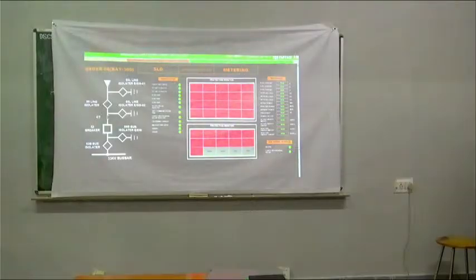How it works: in cable differential, there is some incoming current and some outgoing current. We compare both currents. If the incoming current and outgoing current are the same, it will not operate. If the incoming current is 50 amps and the outgoing current is less than 50, it will react, because somewhere current is leaking. We should isolate the system. That's why the cable differential will operate. That breaker will immediately trip and isolate the circuit from the fault. This is one example for cable differential.